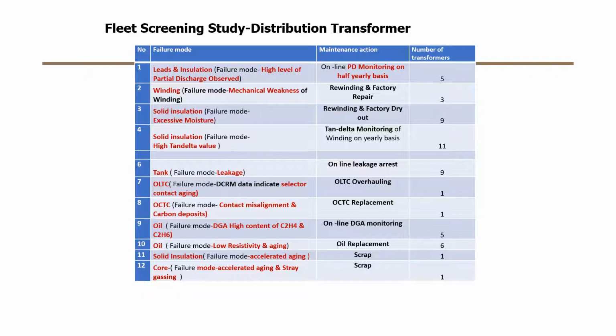Now, winding - mechanical weakness of the winding. There is buckling in the winding, and once that is assessed, you can't keep those transformers in your system. Why? Because if you keep them, two or three system faults will damage the transformer, and then you'll hear that there is a fire in the system. So the origin is mechanical weakness of the winding.